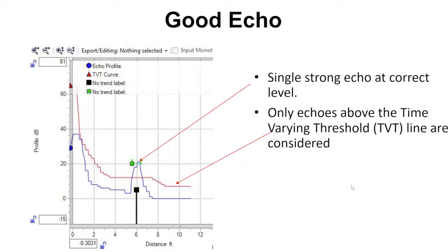In this example the blue line is the echo. Going left to right on the x-axis that's the distance away from the sensor face, so we're looking downward the further we go. The y-axis is the amplitude of our return. So in this case we have a pretty strong return at about the six foot distance from the sensor face.